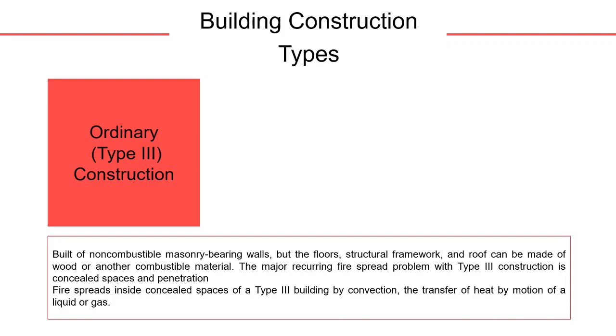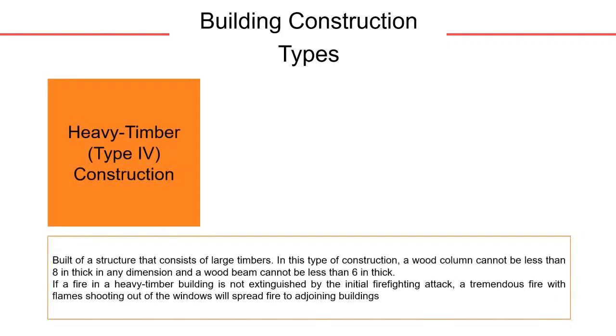These small voids, cavities, and openings through which smoke and fire can spread are found behind the partition walls, floors, and ceilings. Wood studs, floor joists, and suspended ceilings create concealed spaces. Flames can spread vertically several stories or horizontally to adjoining occupancies through concealed spaces. Fires spread inside concealed spaces of a Type 3 building by convection, the transfer of heat by motion of a liquid or gas. Heated fire gases and flames in concealed spaces can travel upwards several floors and break out in the attic space, engulfing the entire building envelope.